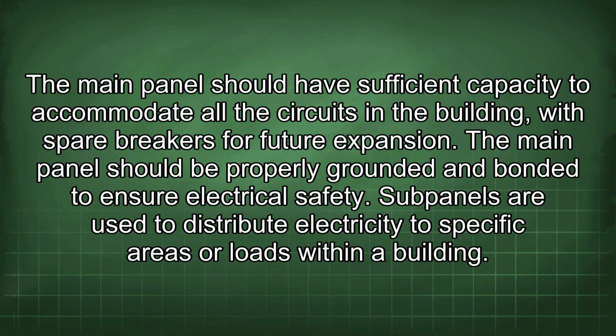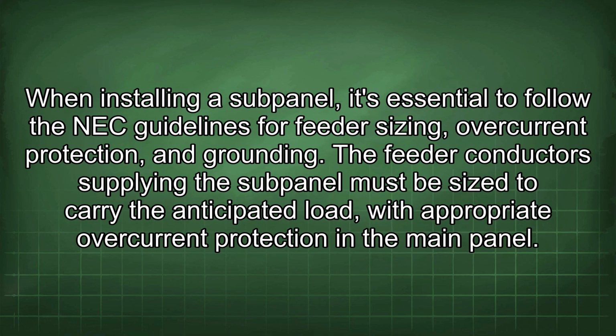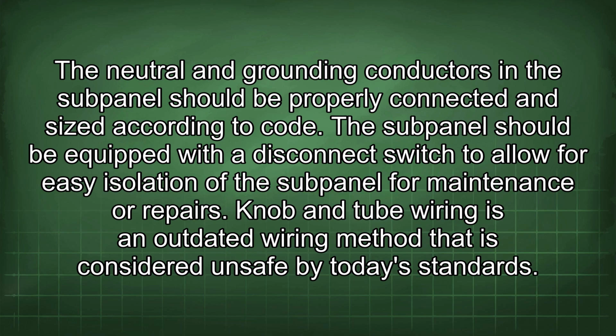Subpanels are used to distribute electricity to specific areas or loads within a building. When installing a subpanel, it's essential to follow the NEC guidelines for feeder sizing, overcurrent protection, and grounding. The feeder conductors supplying the subpanel must be sized to carry the anticipated load, with appropriate overcurrent protection in the main panel. The neutral and grounding conductors in the subpanel should be properly connected and sized according to code.